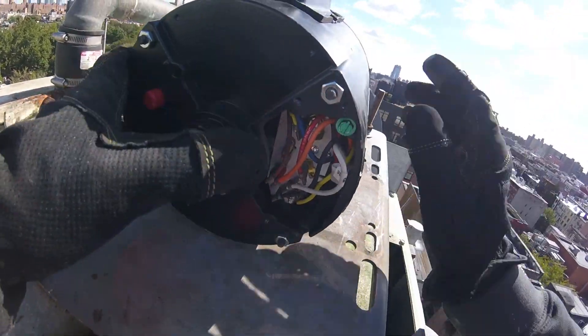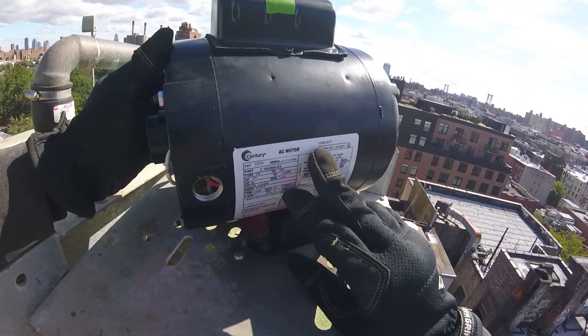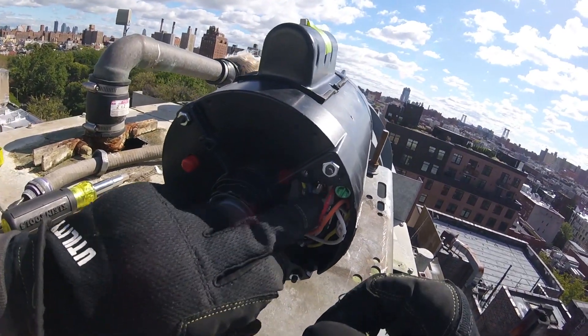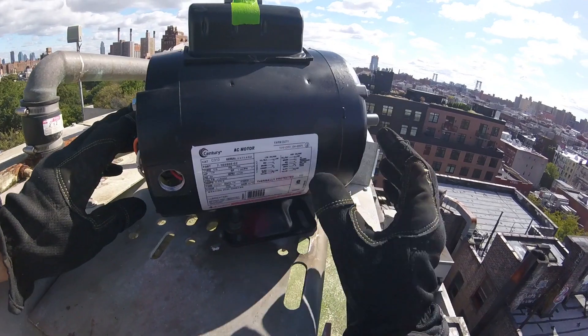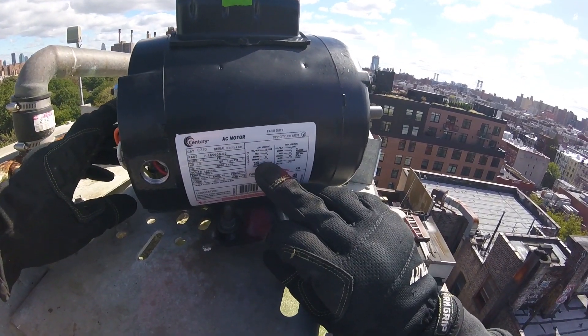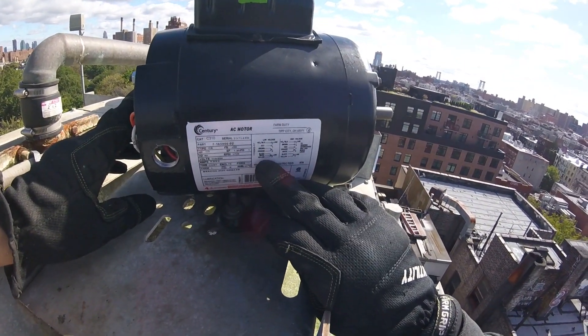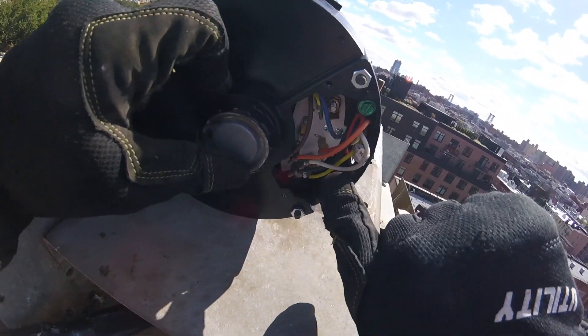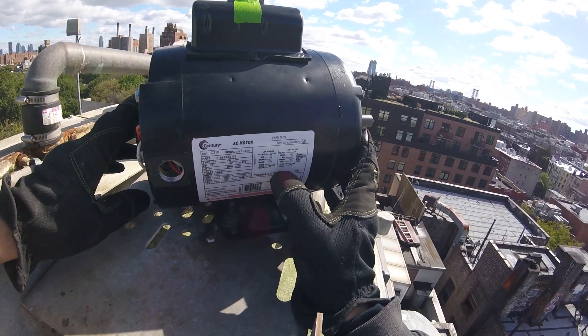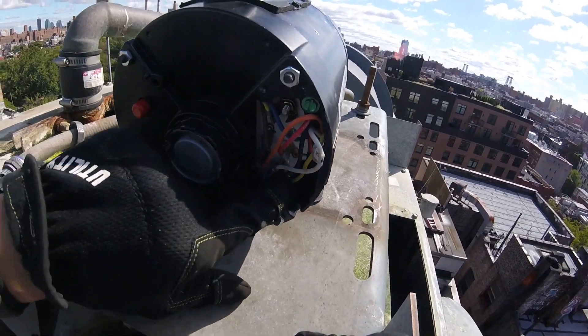If we look here we have six terminals, so we're going to match this up. For low voltage, terminal one should have the yellow and black — here's terminal one, I see a yellow there, there is no black but there is space for another terminal; that goes for line. Red goes to terminal four. Brown and orange go to terminal five. Black, white, and yellow go to terminal six. So we're going to put line to terminal one and neutral goes to terminal six — so we have one and six for power.